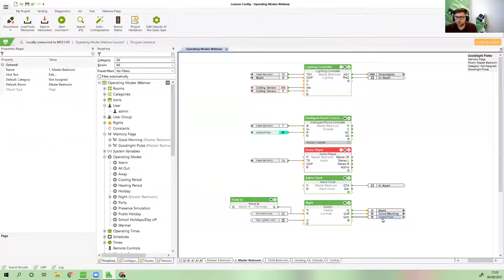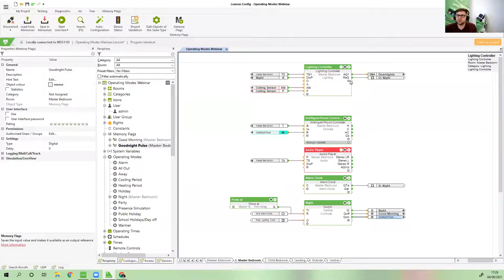This switch block is not going to trigger the night operating mode. It's actually going to trigger an operating mode we have by default called all out. So we'd put all out onto that switch block instead. But there's one other operating mode that we're also going to want to trigger when we leave the house for the day. And this is a very, very special one. It's one that's very, very commonly forgotten. That is presence simulation.